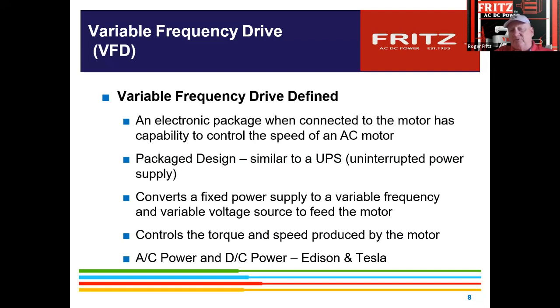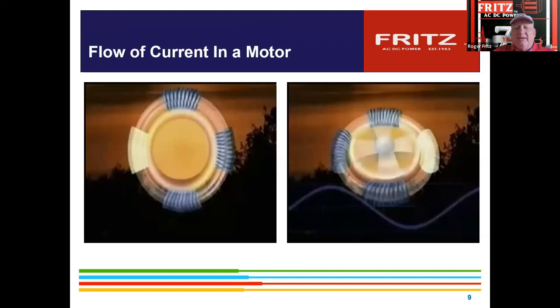It basically controls the torque and the speed of the motor. AC power and DC power: the difference is that Edison was a DC guy and Tesla was the AC guy, and Tesla's the one that won out for Niagara Falls. So again, you've got these rotating fields that we're showing in the video. Because of the sine wave, they will trigger when the north and south poles function on that coil. From that, as we speed up and slow down this frequency and voltage amplitude, we're able to control that AC motor, which before was not able to be done. And that's the nuts and bolts of what we're doing.